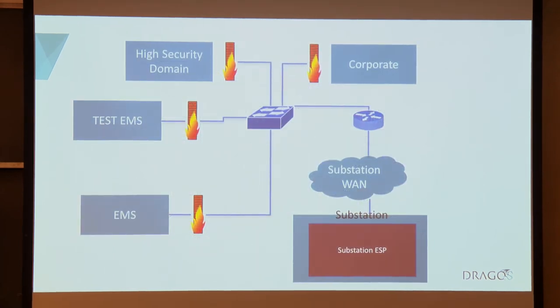A good explanation of what an actual transmission company looks like from the wire: one of our other customers listening on their traffic, this is a map of what they have. They have the core of their operation, which is their energy management system. This is like an extremely large display in a control center operation showing the line chart of all the substations and lines that are either energized or de-energized, with system operators doing dispatch and control based on that, balancing the load, happening at the EMS level.